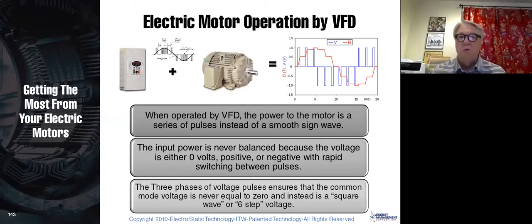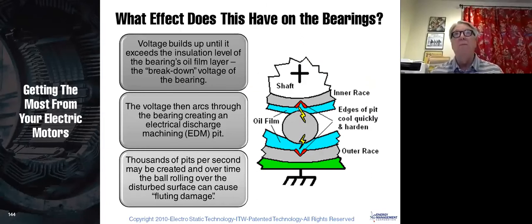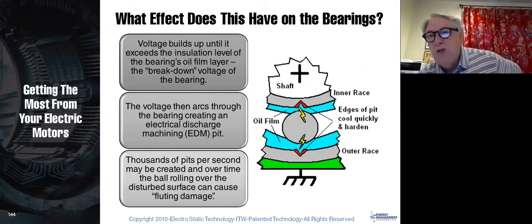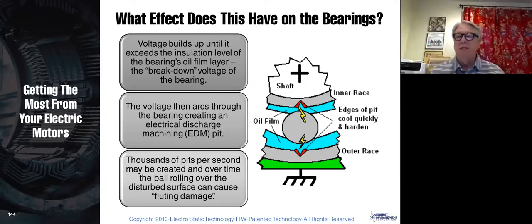No VFD works that way. So when you put the VFD on there, you end up with common mode voltages. In other words, voltages between the shaft of the motor and the frame of the motor. Well, what is between the shaft of the motor and the frame of the motor? The bearings. So as the voltage increases, it gets to a certain point where it will arc through the oil film in that bearing.